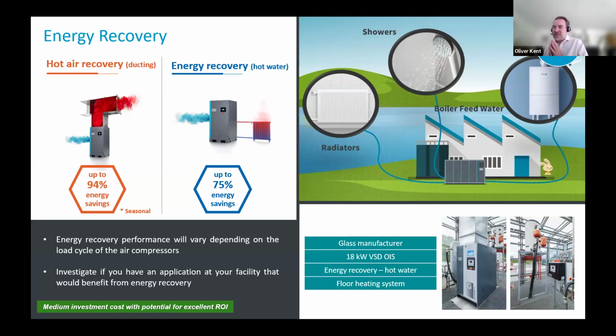On a typical compressed air system, that heat is basically just expelled into the environment. If you've got an air-cooled compressor, it's blown out of the compressor room. If you've got a water-cooled compressor, that warmed cooling water will probably go through a heat exchanger and be blown out into the environment. So how can we reclaim that heat? Well, we can do that by using energy recovery systems. All of that waste heat, we could potentially reclaim. And there are two ways of doing it.